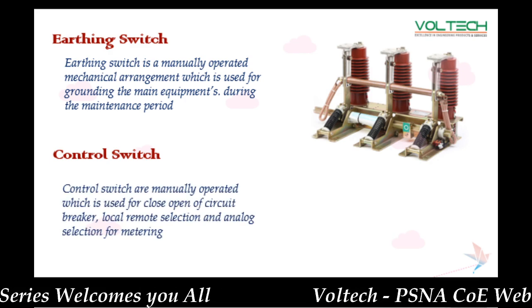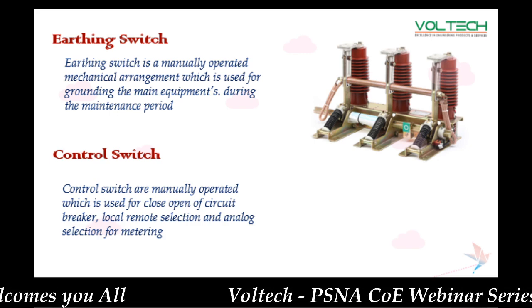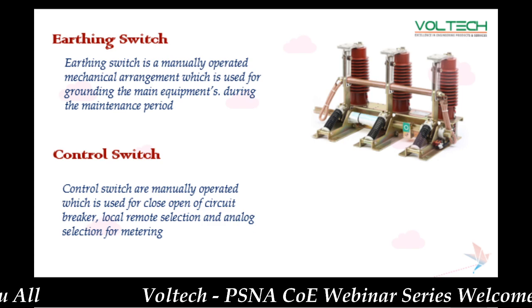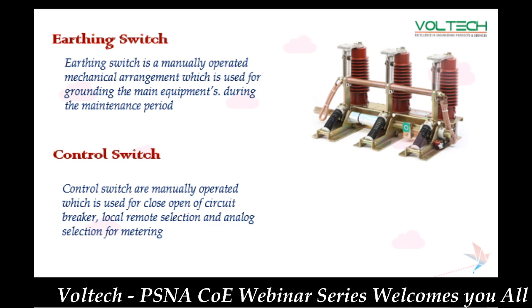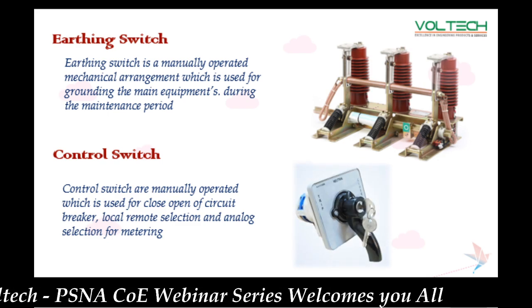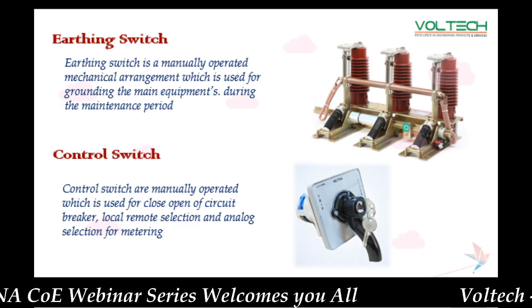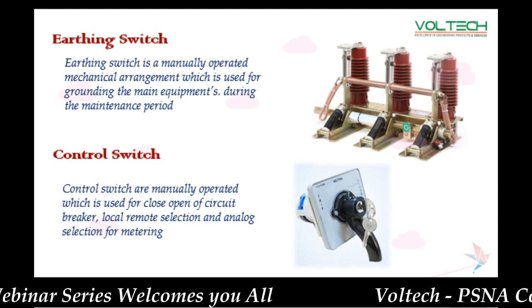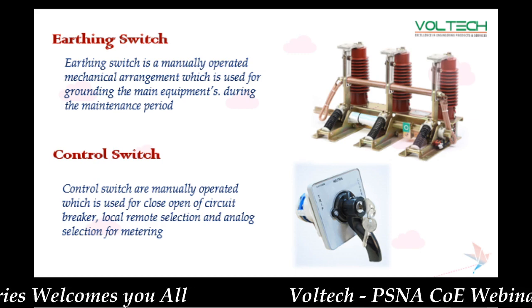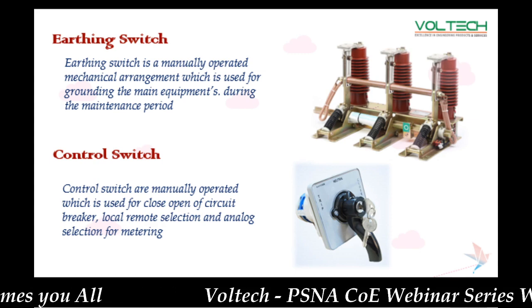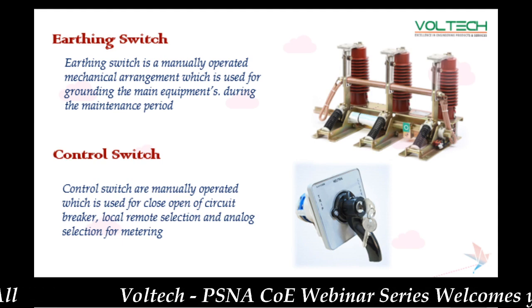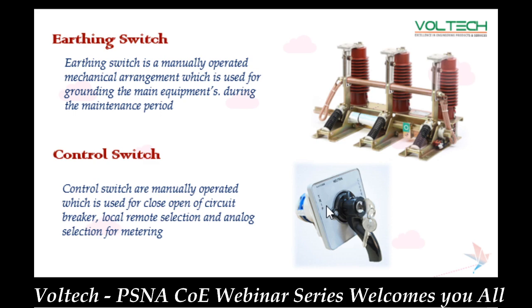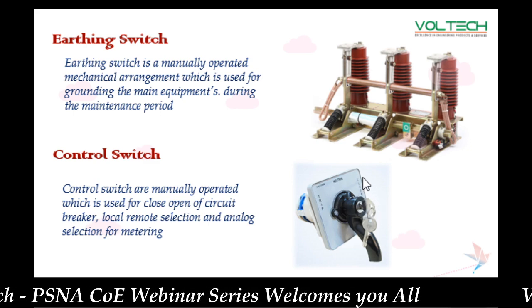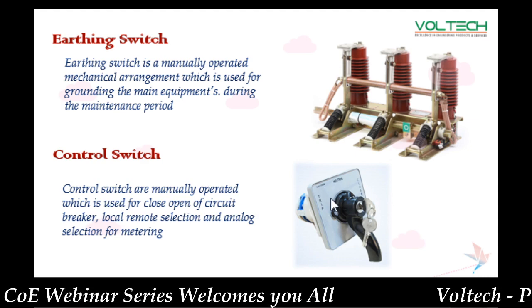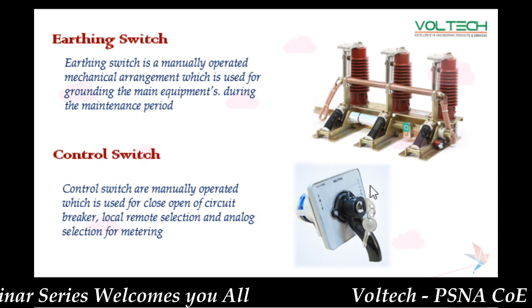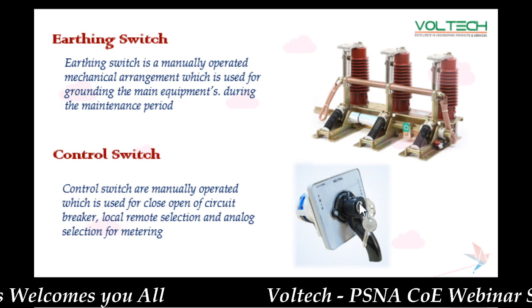The control switch is a simple switch. We use the control switch for operation of the breaker. If you are going to make any operation, close or open or anything else, you can do it with this switch. This is an electrical switch. There is one more option in the breaker: you can close or open the breaker manually. This is an electrically operated switch. We can close or open the breaker using these switches. Here it's written trip and here it's written close. If you turn this switch to this side, it will trip the breaker, that means open the breaker. If you turn to this side, it will close the breaker.